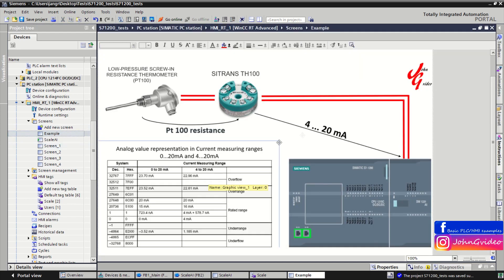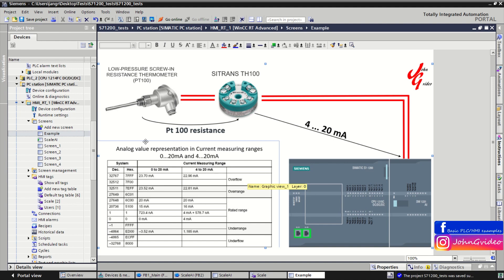As an example for this video we use the scaling of an analog signal input from a temperature sensor. As a range we use a current input with a range from 4mA to 20mA. As you can see in the table showing analog value representation in current measuring ranges from 0 to 20mA and 4 to 20mA, in your PLC you have a representation of the analog input signal as decimal numbers from 0 to 27648.